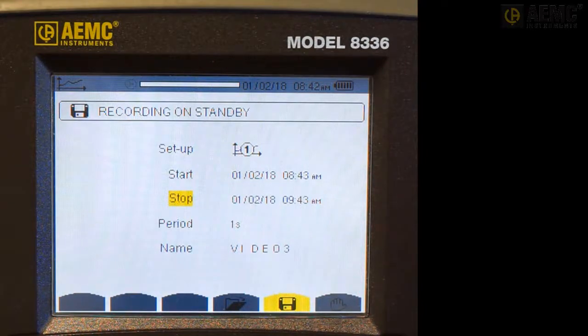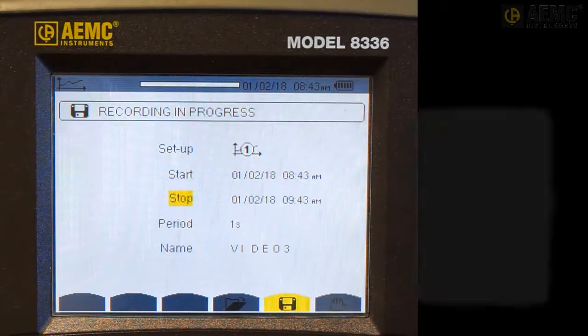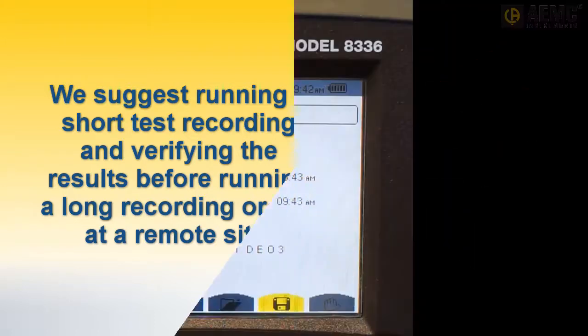When the recording is active, the message Recording in Progress appears on the screen. As a good practice, before you run a long recording, or one at a remote site, we recommend running a short test recording and viewing it to ensure it contains meaningful data. This helps identify issues, such as current probes connected in reverse directions, or incorrect current and voltage phase connections.